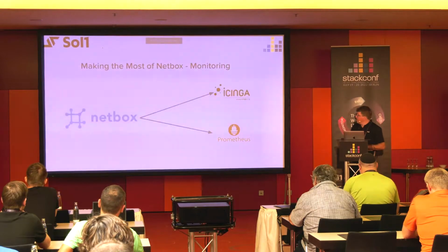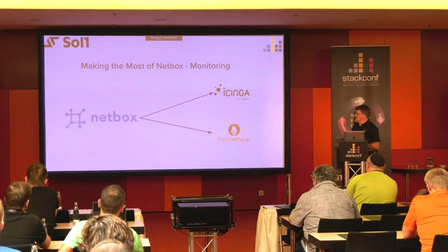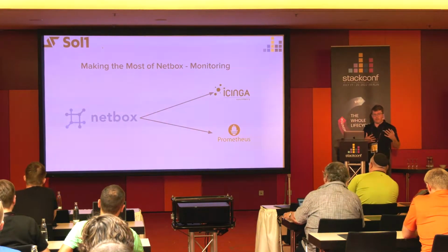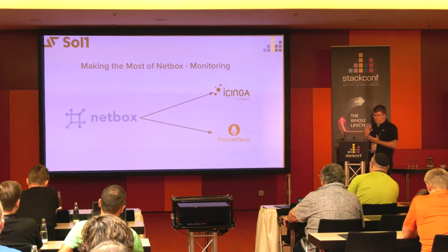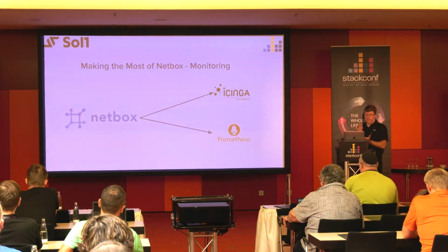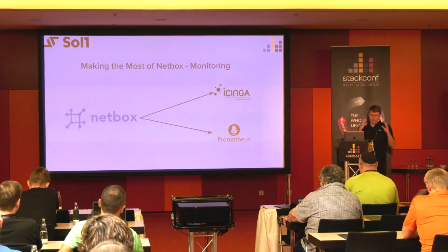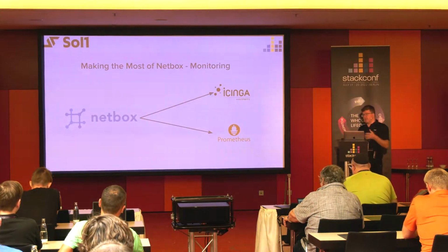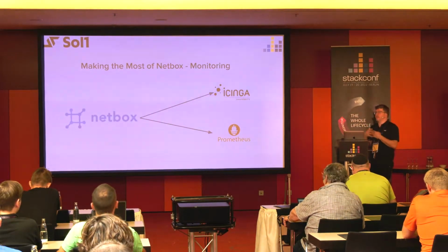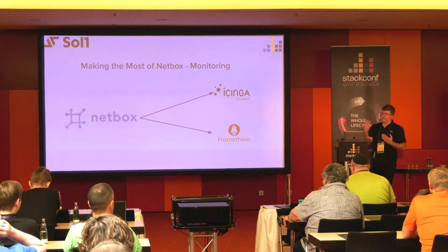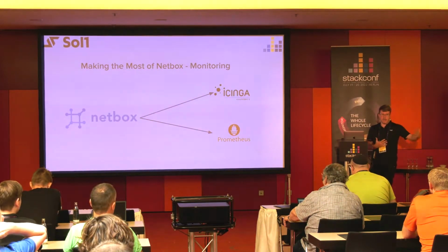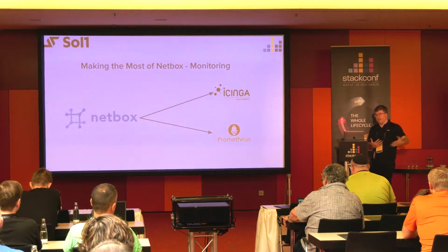So the next thing we've been working on is integrating it with monitoring. So we enter the data into Netbox, we pull it all out of those spreadsheets, chuck it in Netbox, and then we've written a tool that connects Icinga Director and Netbox, so it can poll the API of Netbox, pull the devices out, and automatically create monitoring objects, services, plumb in the groups, notification groups from contacts. All those things get plumbed in right from Netbox. So an engineer doesn't have to actually configure the monitoring at all. They simply document the device in a structured way, and that automatically starts to get monitored.